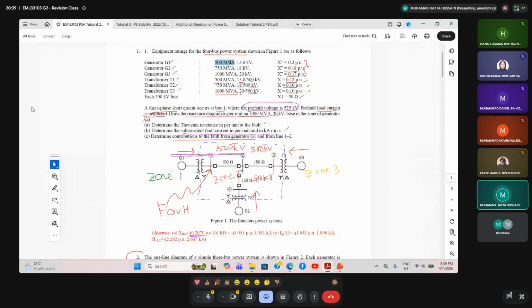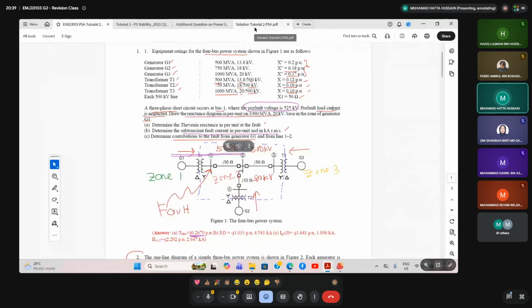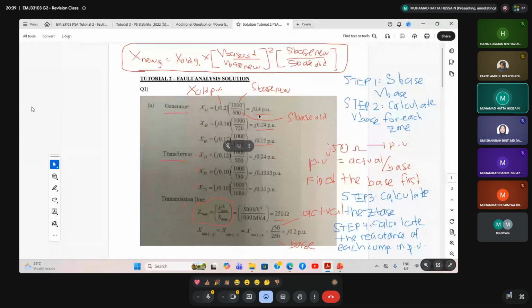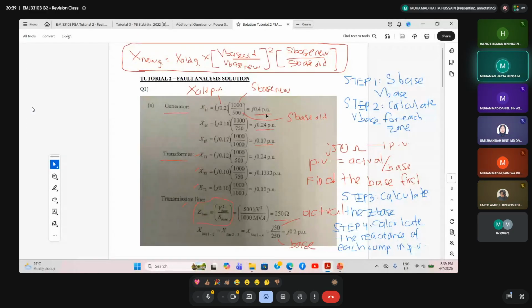But for the S base new, starting from generator at zone 1, going to zone 2 and zone 3, we have to use 1000 MVA. This is basic that all of you should know from power system engineering. So from here we get the exact value for xg1 new, which is J0.4 per unit when calculated using this standard formula.